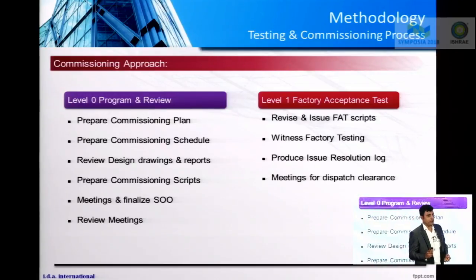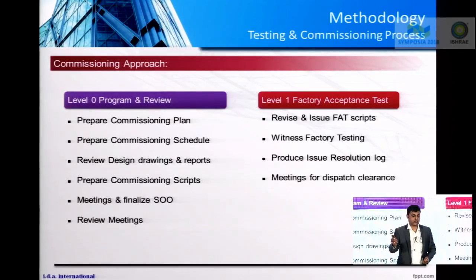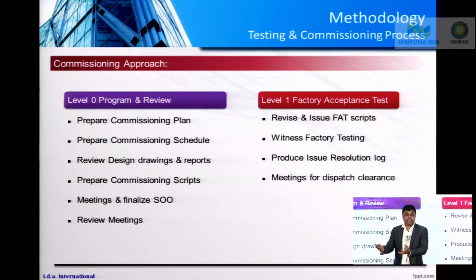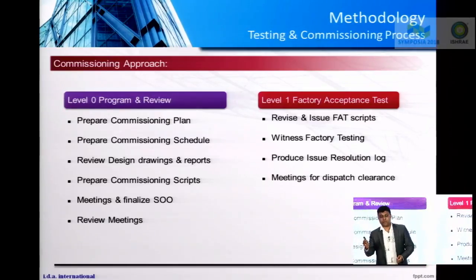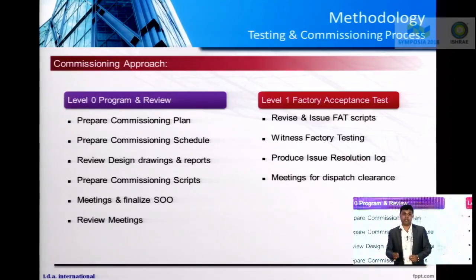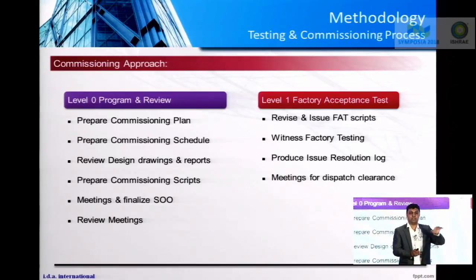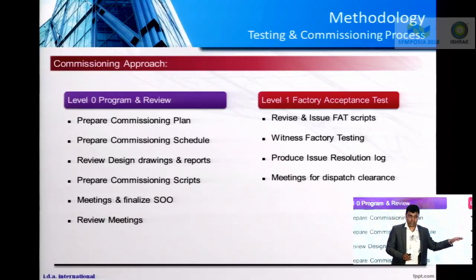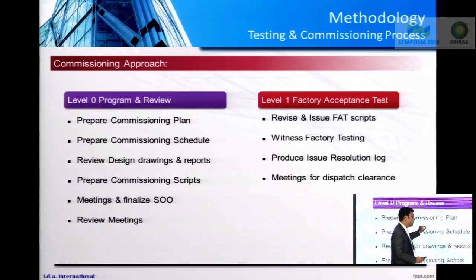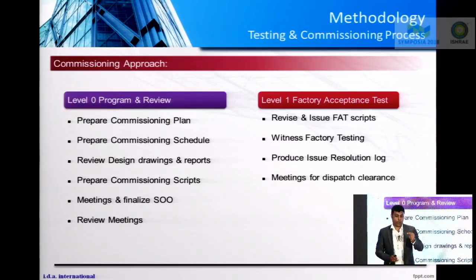You really don't want an argument during the construction stage or a fight with the GC, where I have requested an 8-hour burn-in test of a generator, and he says, no, I'm not going to do it, it was not part of my scope of works. So it is very important that all these commissioning documents form part of your tender package. And that's one of the reasons they have to be produced right at level 0.